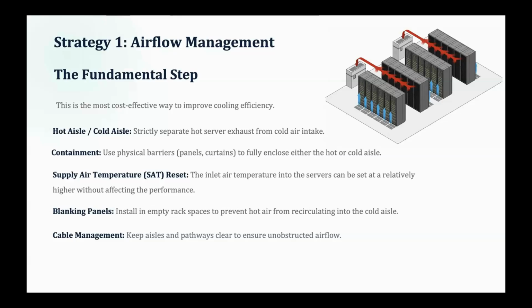So hot air cold air containment is very critical, and it is also one of the easiest ways to improve the airflow management in the data center and achieve efficiency as well. Second one is supply air temperature reset. Supply air temperature is the temperature of the conditioned air being supplied to the servers.